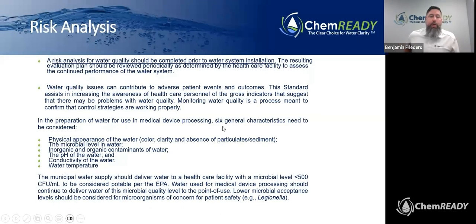The risk analysis for water quality should be completed prior to water system installation. I know a lot of facilities already have water systems. That doesn't mean that you should not do this. The risk analysis still needs to be performed for your existing system to understand what parameters your system is capable of creating and what the risks associated with each piece of equipment could be and how they could contribute to adverse patient effects or outcomes.